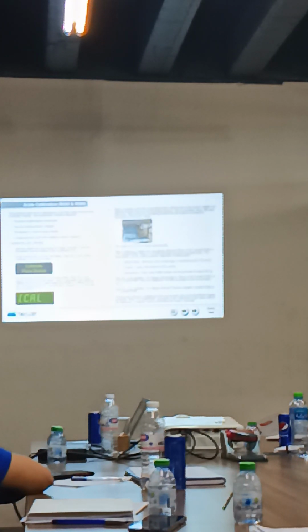Okay, so this is the scale calibration. This is really the only thing you have to do to this machine, because you have to tell the machine what weight is on those scales. Okay, so I'll just read through this quickly. So again, you're not going to remember this. This is in the manual, so if you need to do this, you're going to get the manual.